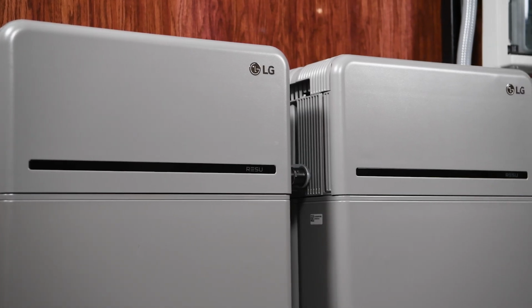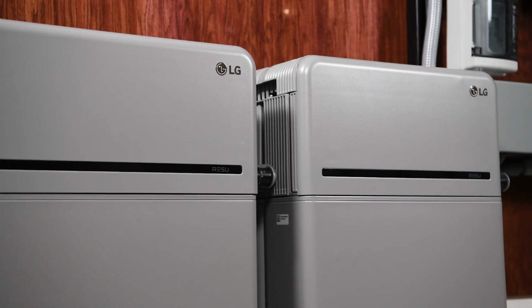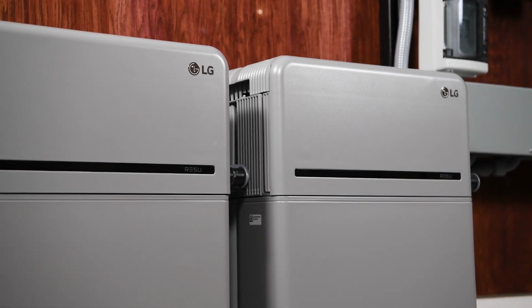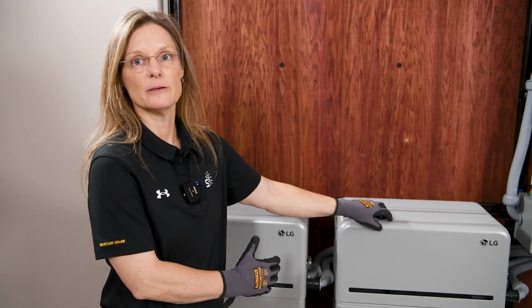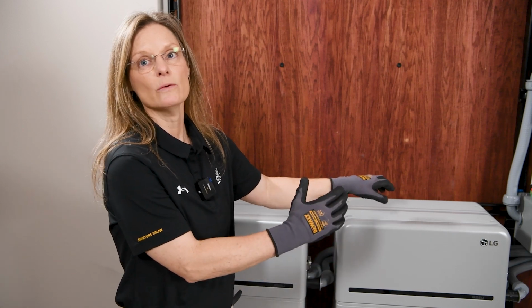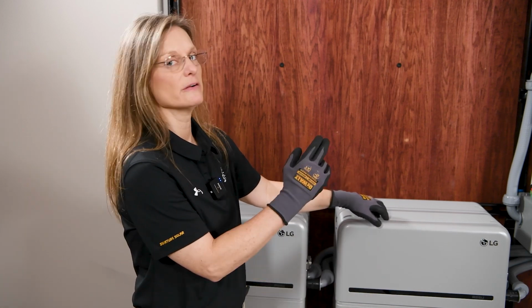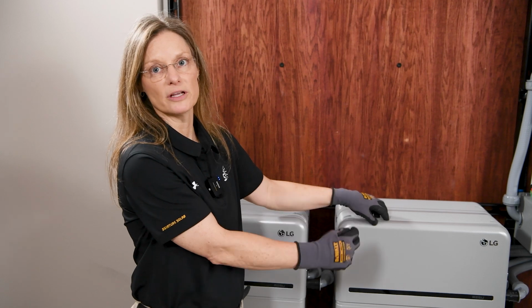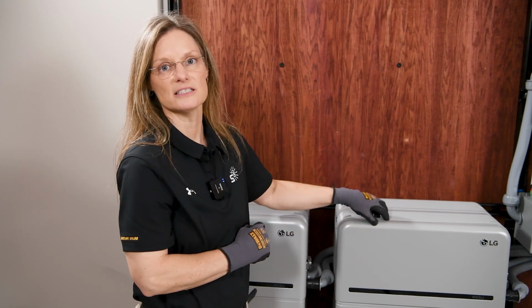We'll daisy chain these two batteries together. We'll set up communications to our primary battery, connect it to our secondary battery, and from the secondary battery set up communications directly to the inverter, using the same communications cable we just connected inside the inverter.